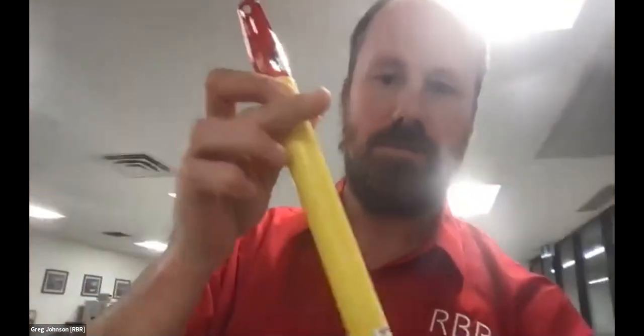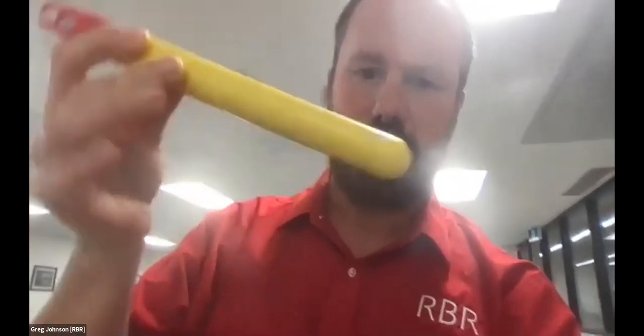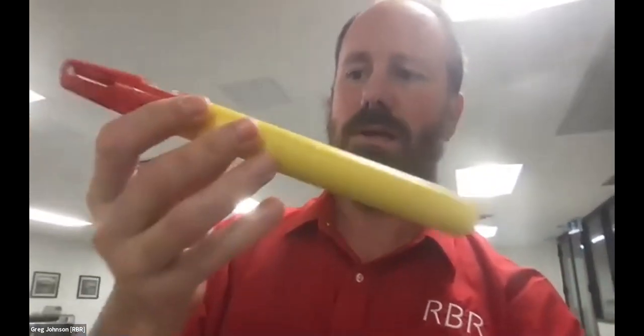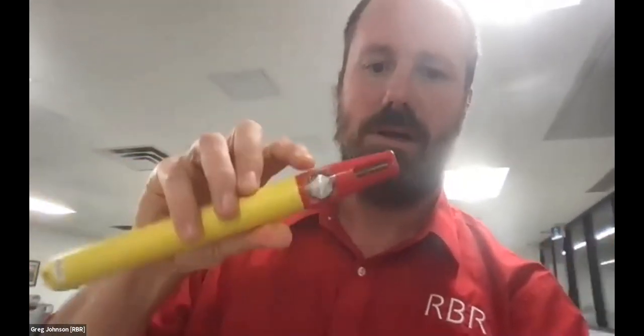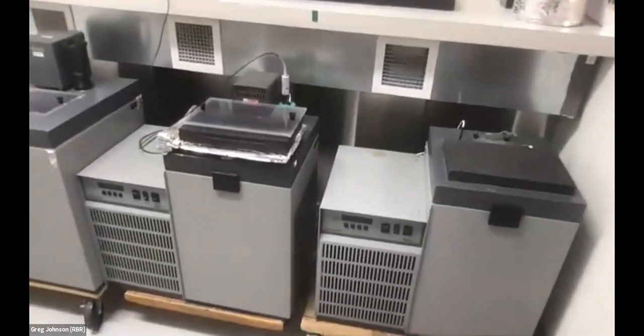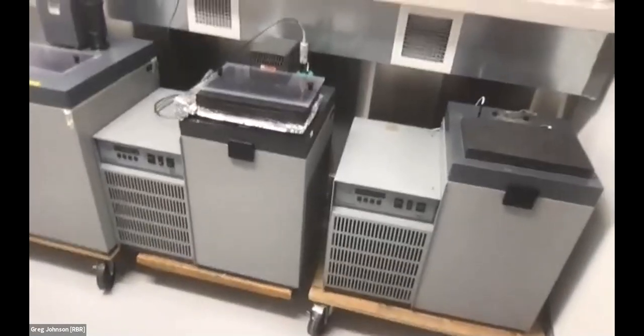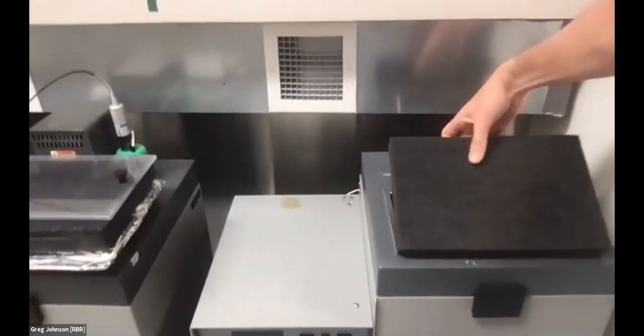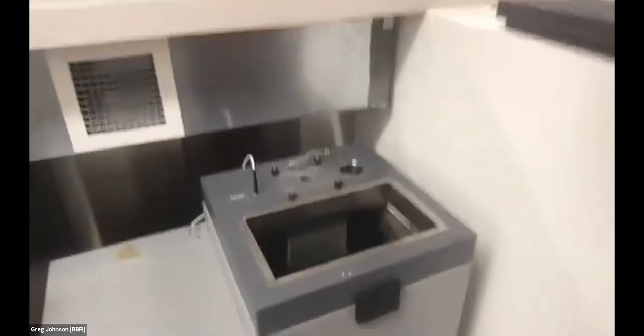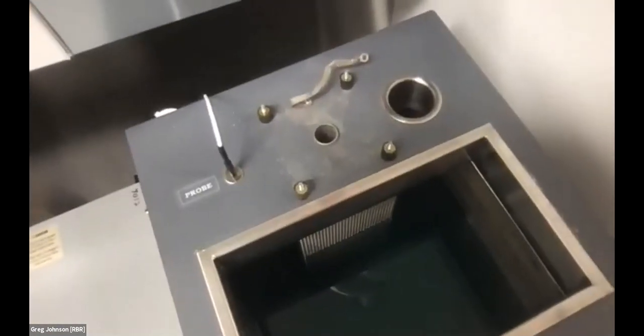I have one here that I've just lifted up. These are our compact logger family. This one's not yet labeled as it's in the cal lab, and it's just been undergoing pressure and temperature calibration. How do we do that calibration? Well, we put them into baths like these ones in this section. So these are small water baths, which are filled with a slightly alarming looking green water.